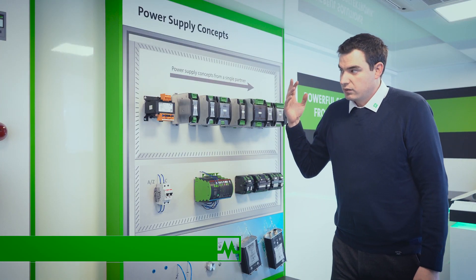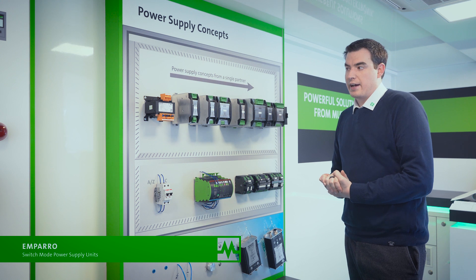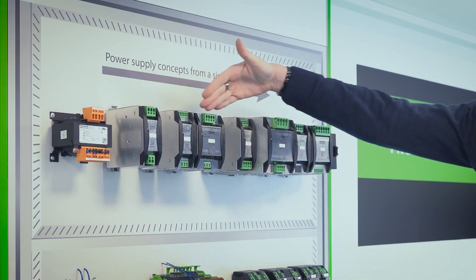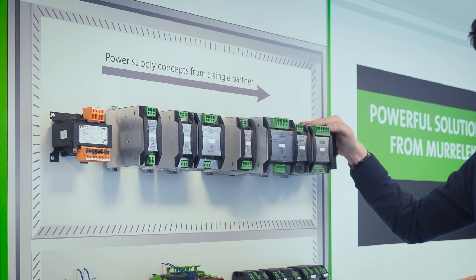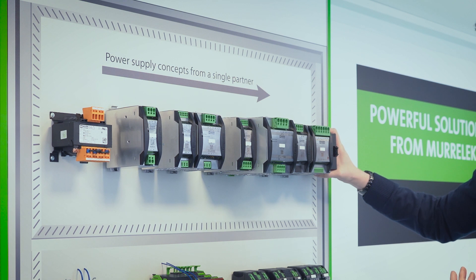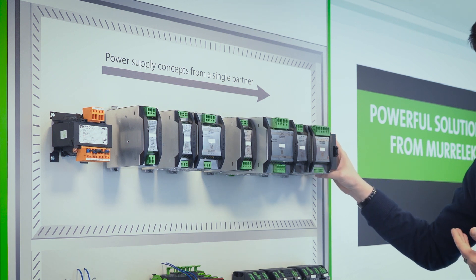With the 24 volt switch mode power supplies, we have our premium range product, which is Emparro. As you can see, it covers a vast range of modules. Starting with the UPS — our UPS system is quite independent in that it actively monitors the battery not just for temperature, but also for charge and capacity, by monitoring the voltage and the resistance of the battery as it charges and discharges.